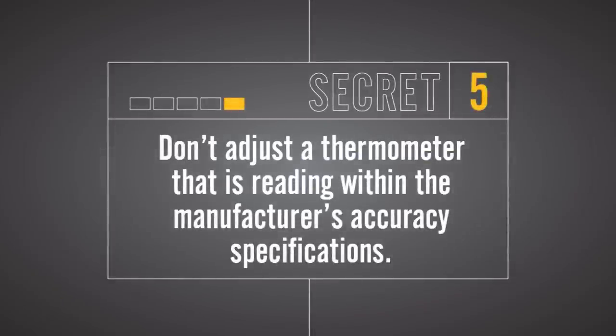Secret number five: don't adjust a thermometer that is reading within the manufacturer's accuracy specifications.